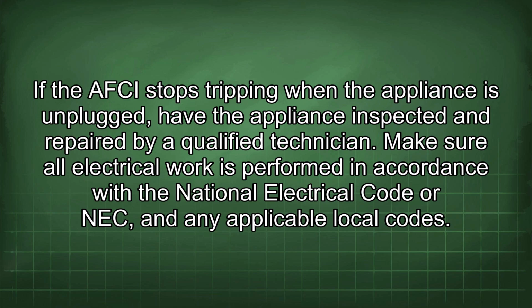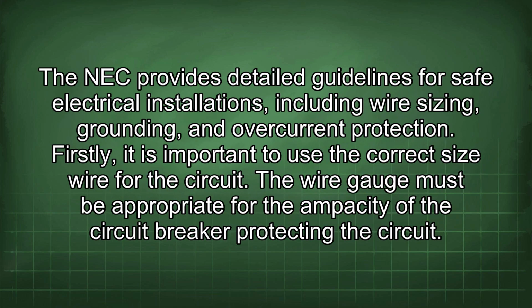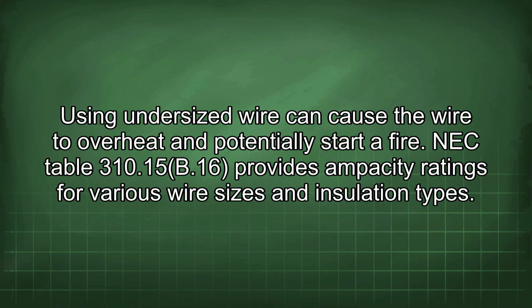Make sure all electrical work is performed in accordance with the National Electrical Code, or NEC, and any applicable local codes. The NEC provides detailed guidelines for safe electrical installations, including wire sizing, grounding, and overcurrent protection. Firstly, it is important to use the correct size wire for the circuit. The wire gauge must be appropriate for the ampacity of the circuit breaker protecting the circuit. Using undersized wire can cause the wire to overheat and potentially start a fire.